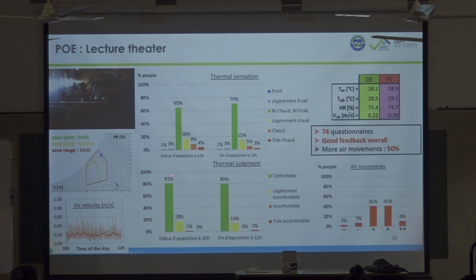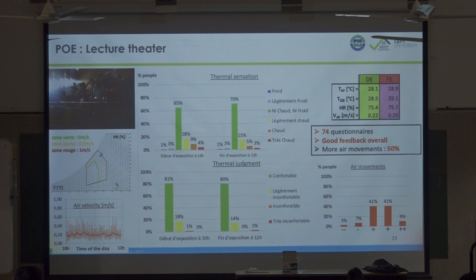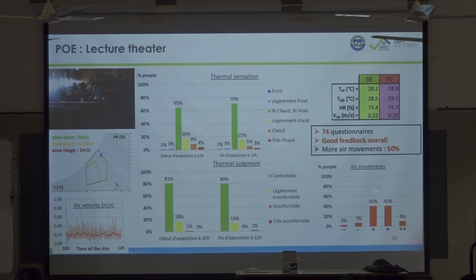Thermal judgment — comfortable vs. uncomfortable — is slightly different from thermal sensation. At the beginning 81 percent felt comfortable; at the end the same 80 percent. There is a difference between the thermal sensation vote and the thermal judgment vote because some people say they feel slightly warm but are still comfortable. Despite the low air velocity, people are more or less happy.